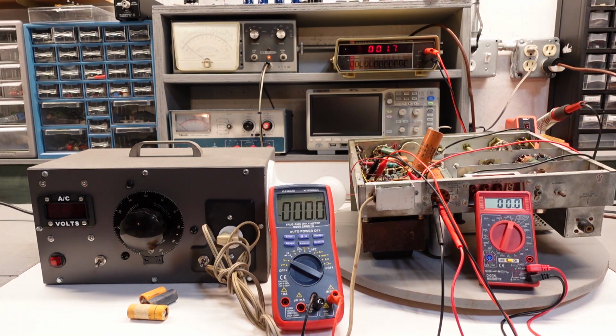In this case, because of how unique this transformer is, there are 4 separate secondary taps that I need to monitor. I've got 4 voltmeters hooked up here so I can look at everything simultaneously. I like to do this because you could just check it with a single voltmeter, but that's a little more risky because you're probing around some very high voltage in some cases, and it's just safer if I have everything instrumented and keep my hands away from the rig while I've got AC voltage applied to it.